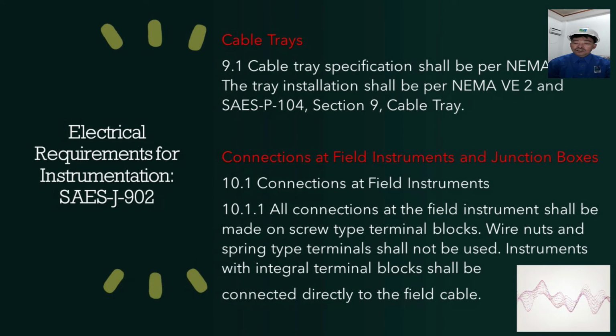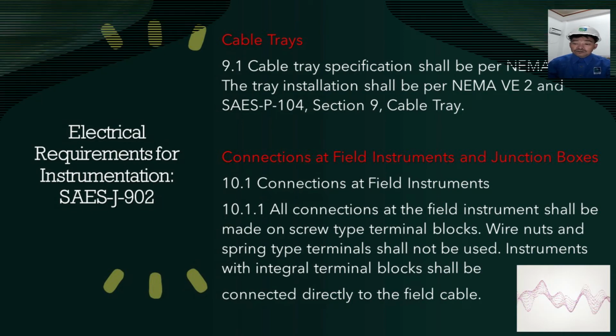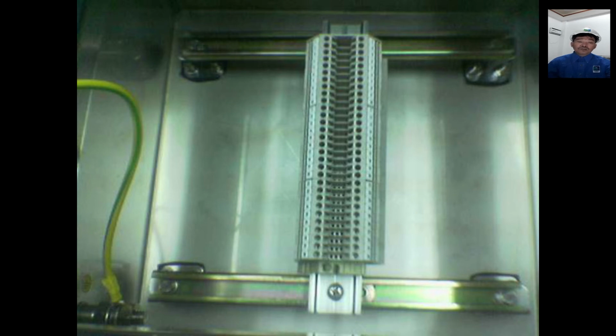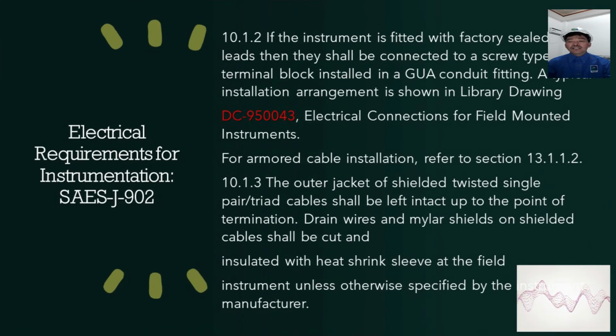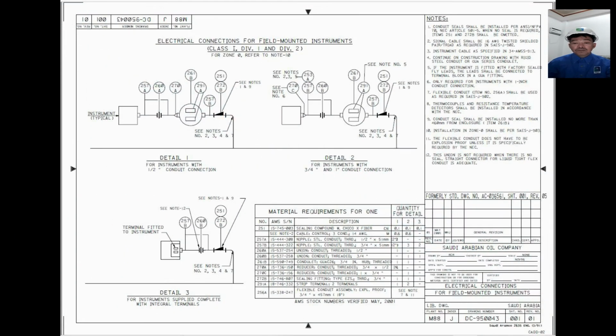So we have the connection at field instruments and junction boxes. All connections at the field instrument shall be made on screw type terminal blocks. So we're going to use terminal blocks. Wire nuts and spring nut type terminals shall not be used. Instruments with an integral terminal block shall be connected directly to the field cable. So only terminal blocks are allowed. Wire nuts, like the ones we use in lighting fixtures, are not allowed. If the instrument is fitted with factory sealed fly leads, then they shall be connected to a screw type terminal block installed in a GUA conduit fitting. Typical installation arrangement is shown in the library drawing. This is DC-950043, the electrical connection for field mounted instruments.